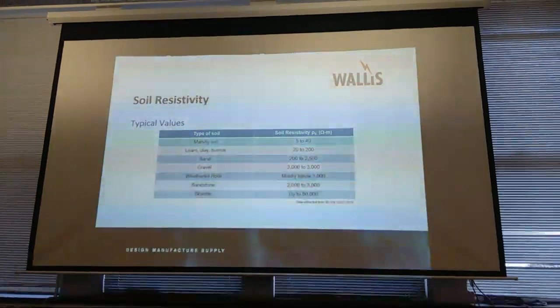Typical values, out of 50522. Again, you can see that the variances are massive. I can speak for Nottingham, because that's where we're from. We've got a top layer of nice red clay where it's somewhere between 20 and 200 ohms per metre. But then down by me, we've got sandstone at 2,000 to 3,000 ohms per metre. So it depends where you are in the city as to what coverage you've got. I think it'll be very similar around here, the same right across the country. So for central London, where they've got metres and metres of the lovely London clay, you can just get half an ohm for knocking an earth rod in the ground.